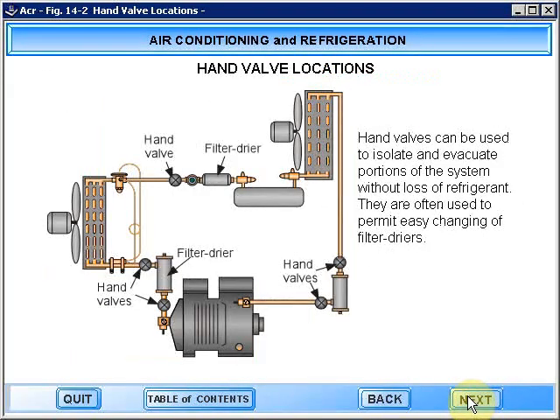Hand valves can be used to isolate and evacuate portions of the system without loss of refrigerant. They are often used to permit easy changing of filter dryers.